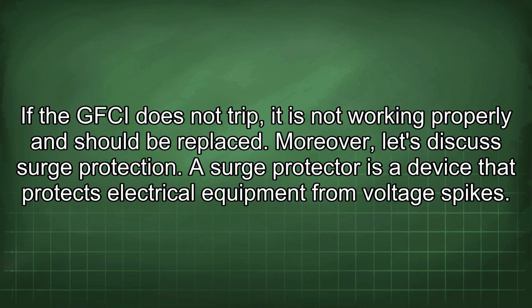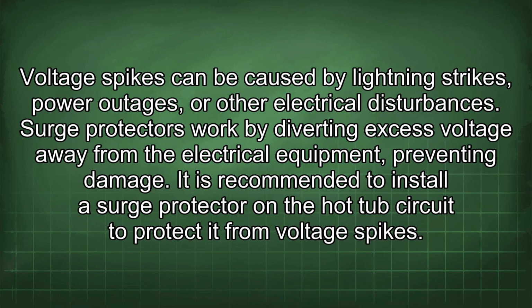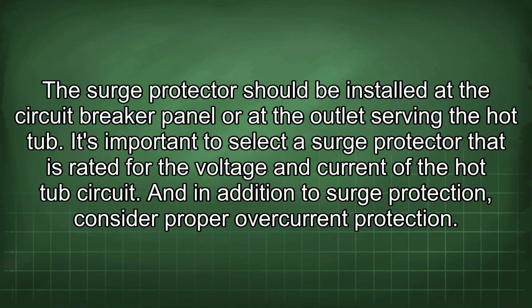Moreover, let's discuss surge protection. A surge protector is a device that protects electrical equipment from voltage spikes. Voltage spikes can be caused by lightning strikes, power outages, or other electrical disturbances. Surge protectors work by diverting excess voltage away from the electrical equipment, preventing damage. It is recommended to install a surge protector on the hot tub circuit to protect it from voltage spikes. The surge protector should be installed at the circuit breaker panel or at the outlet serving the hot tub. It's important to select a surge protector that is rated for the voltage and current of the hot tub circuit.